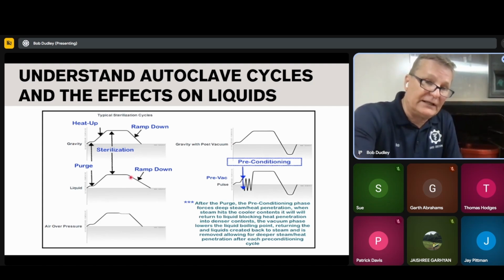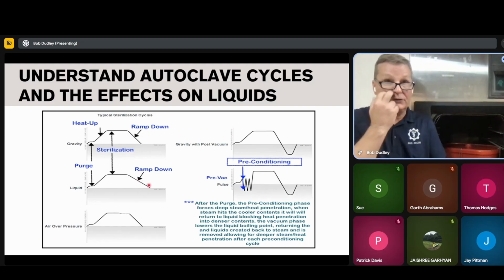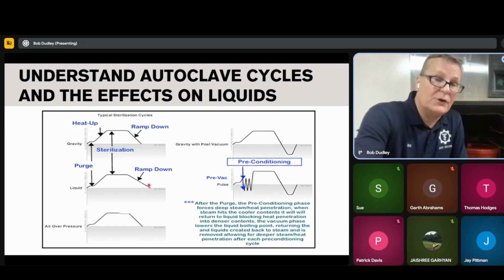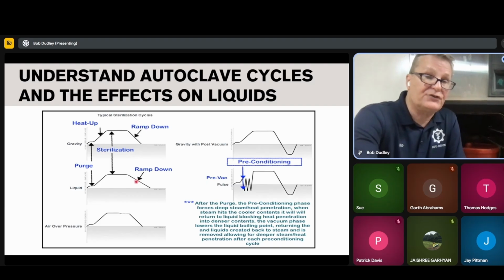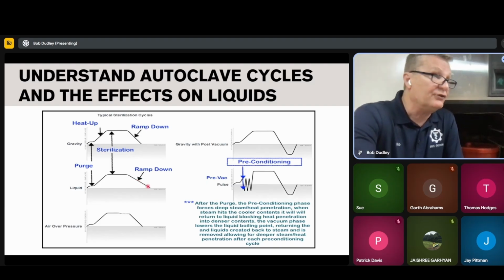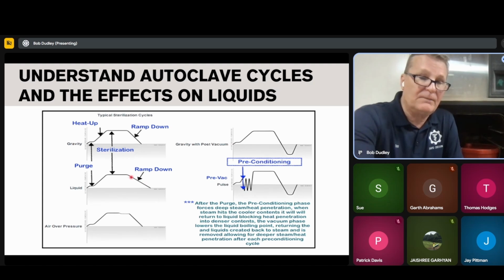And what it's doing is it's taking the heat out of the jacket and the chamber at the same time. So that allows the liquids to cool off for 2 or 3 minutes. Then it takes the pressure off of it. Then it just keeps going down, down, down. That's why your liquid cycles take such a long time. You're bleeding the pressure and the temperature down, and it should take approximately 50 minutes to an hour.